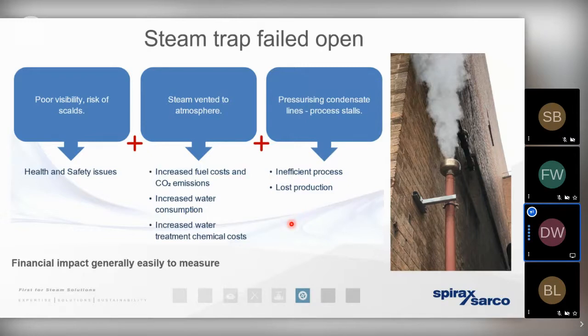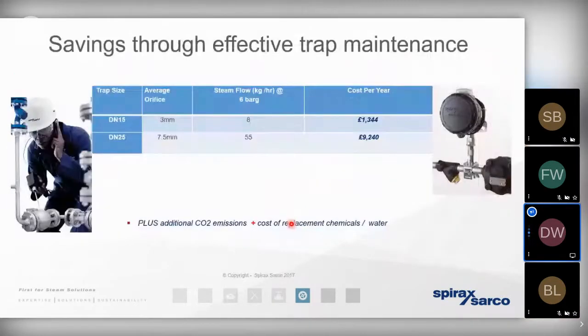And that's because if we know the size of the steam trap that we have and the pressure that we're distributing the steam at, if we know the operational hours per year of the steam plant, and if we've benchmarked our cost of steam, then the orifice size tells us we can very, very easily calculate how much energy we're losing to atmosphere every year.